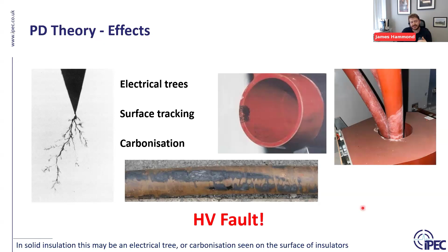And this PD is damaging the insulator mechanically, thermally, and chemically as well. It's a very common reason for failure. On average about 80% of HV failures are caused by, or at least have the root cause being, partial discharge. And that's mainly because it's invisible. It's only detected once you've got the instrumentation, or if something catastrophic happens. That's the only time you ever find out that PD was ever there at all.